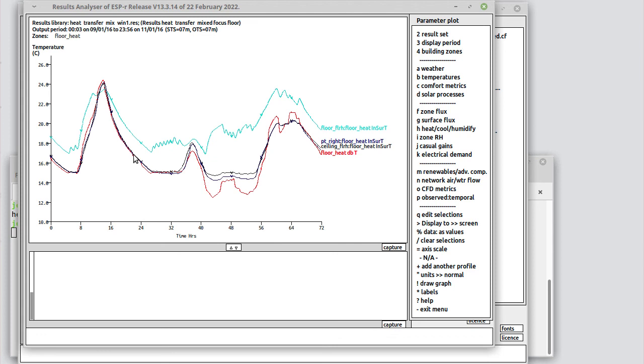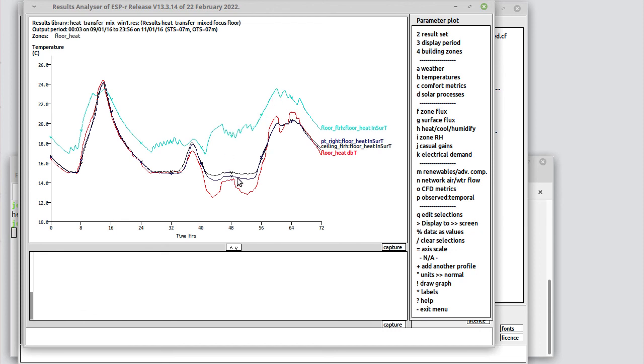And then it gradually drifts down to around 15 degrees, which was the night set point. We then have a brief warm-up. The floor is attempting to be at 20 degrees and then going up to 24 degrees. So in order to maintain the temperature overnight, the floor is still somewhat active. And then the temperature ramps up during the next day to get us to our 20 degrees. So that's a graphical look at things.